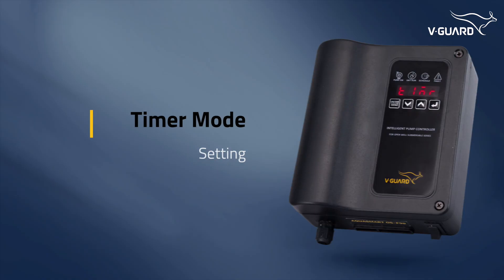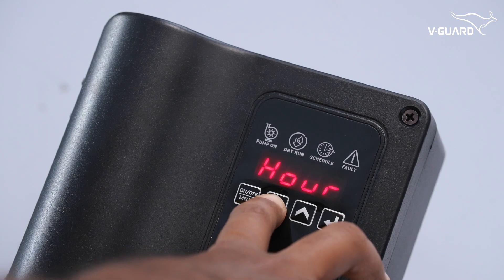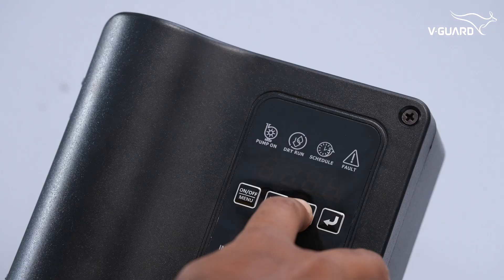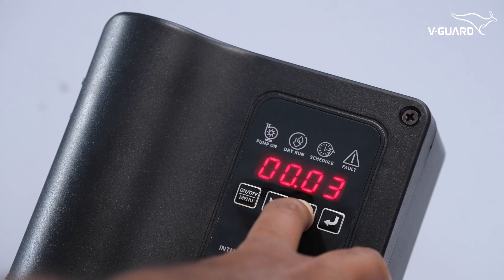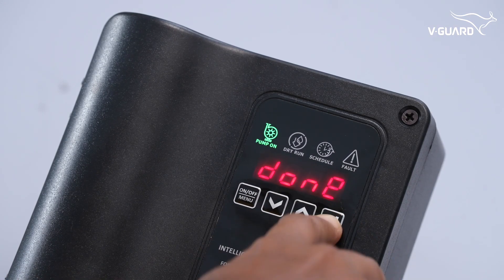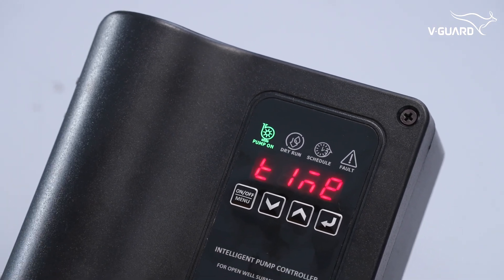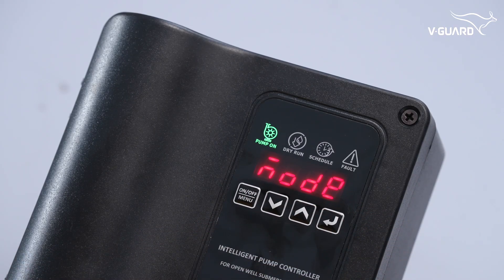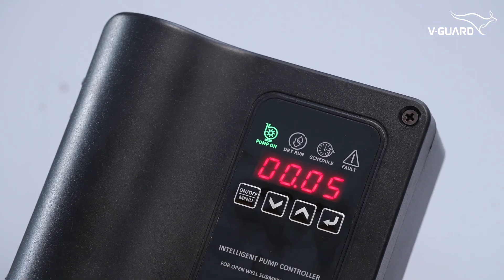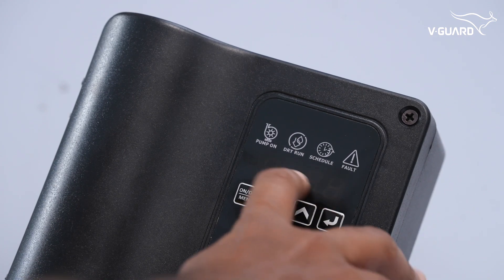The timer mode allows the pump to operate for a specified duration without automation. Press menu and navigate to the TIME option. It shows OFF, indicating the timer is currently not active. Select the duration you want the pump to work for — from 1 minute to 24 hours — and press enter. When active, the timer mode overrides other operational modes such as scheduler and float switch. To turn it off, enter the timer mode and reduce the time until it shows OFF, then press enter.